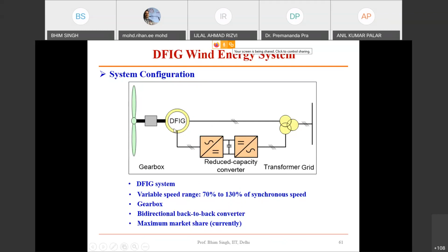And now slip is 30%. So if you want to give reactive power from the stator, you have to give, let us say, 100%, but here you have to give only 30%. That is a major benefit: the amount of reactive power required reduces if you give it from the rotor side, and the stator power factor is unity. Compared to 0.8 power factor on the stator, with unity you will be able to generate around 120 to 125% directly from the stator, corresponding to 130% speed, maximum power. And because the machine is operating at 30% slip, it is able to follow.